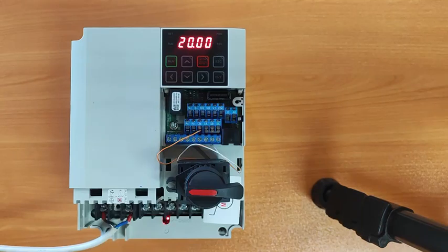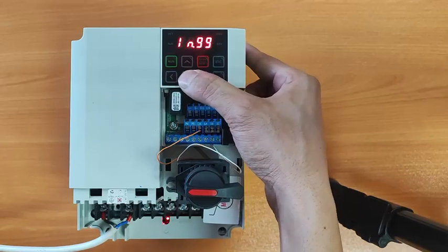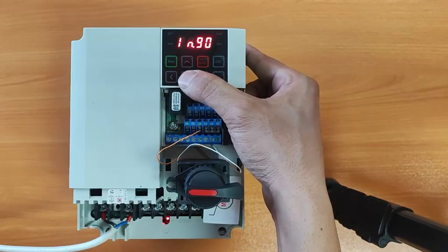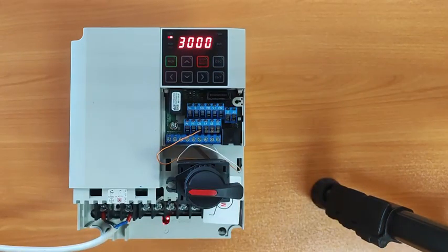Alright, as we said, if we want to set up on delay and off delay for the digital inputs on this inverter, we need to enter the parameter group for this. In parameter IN85, we have to set the delay for the digital input to turn on, and in parameter IN86, we can apply the delay for turning off. Now I've entered parameter IN85 and I'm setting its value to 3,000 milliseconds or 3 seconds, which means that if I activate the digital input, which I've connected here, the inverter will start after 3 seconds.